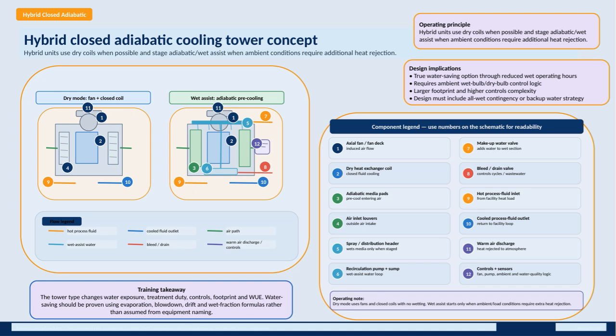From a training perspective, understanding this tower type is critical because it affects water exposure and treatment needs, control strategies, and overall water use efficiency. We can't just assume water savings based on the name. Instead, we need to calculate evaporation, blowdown, drift, and wet fraction formulas to prove actual water efficiency.